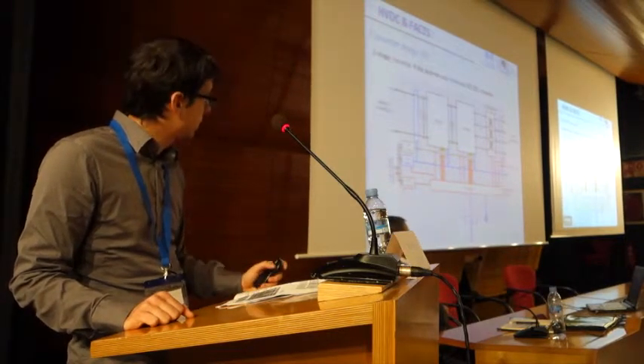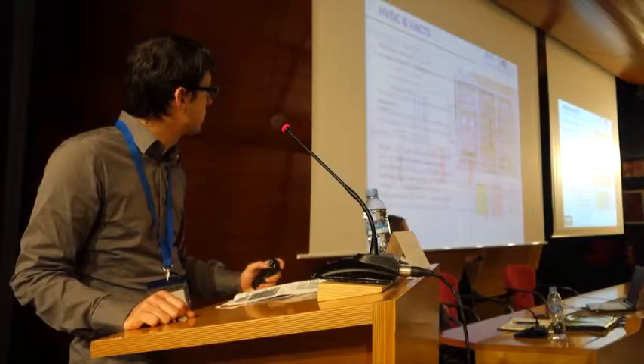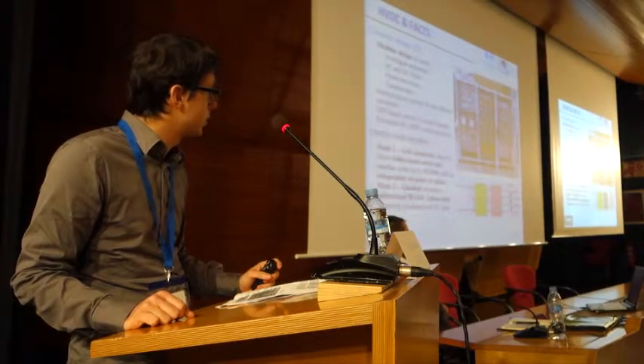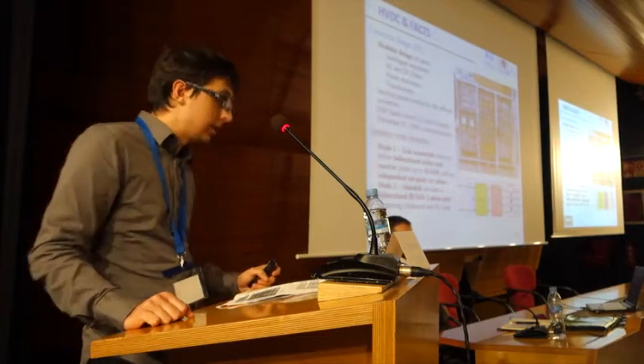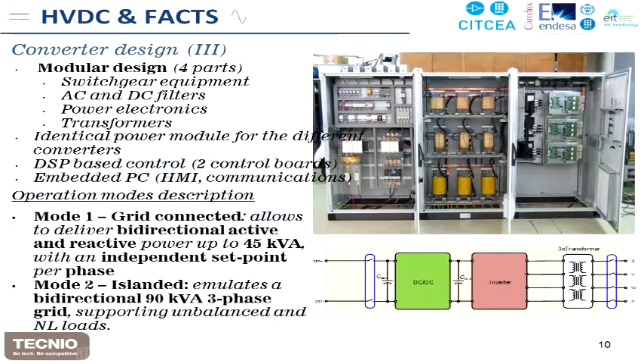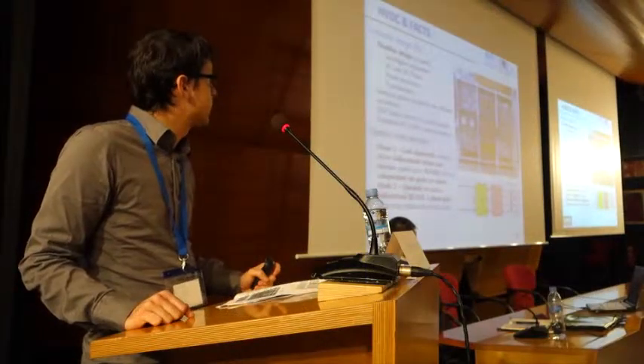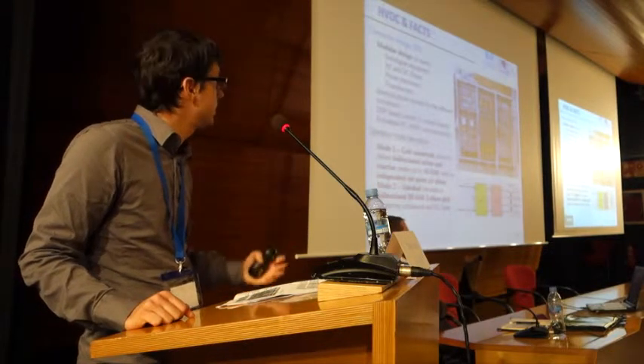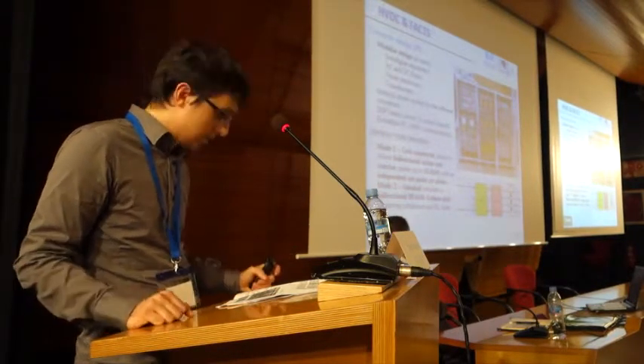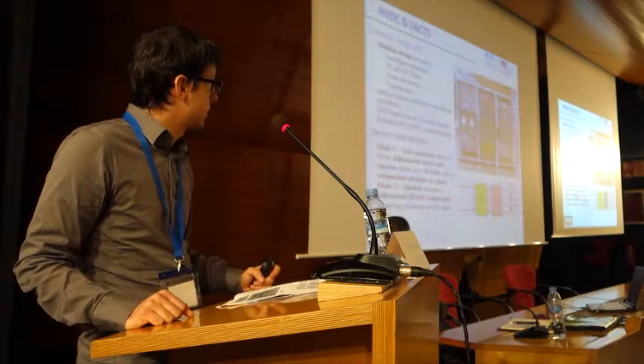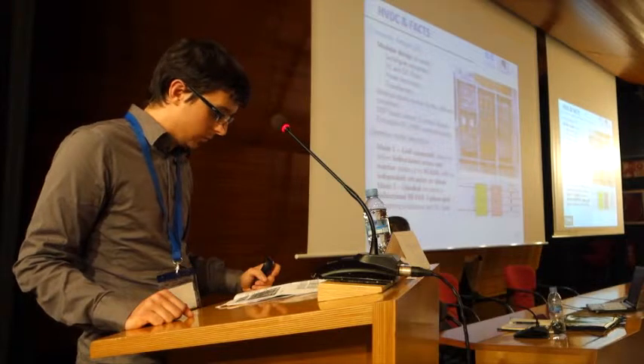Well, this is the schematic of the system that we are proposing, and here you can see a picture of the real system. Basically, it's constituted by four parts. There is an electrical cabinet that allows us to house the switchgear equipment, the DC and AC filters, and the power electronics, and the transformer are behind that electrical cabinet, so you cannot see them in the photograph. We have decided to use identical power modules in order to have more flexibility to replace one if something happens. And this will have some consequences that some slides later I will explain.